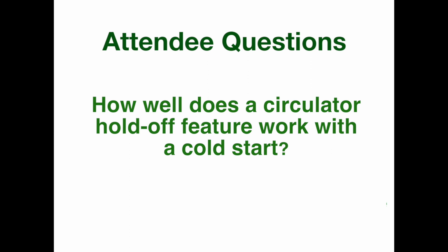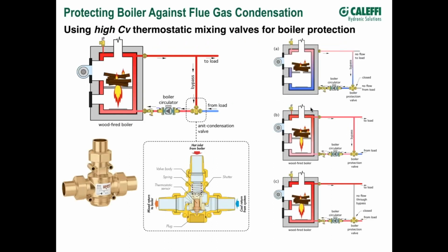Yeah, if you go back to that, there you go. I think the Caleffi one we offer comes with a 130, and I believe you can get two other temperatures. I think you can get down to 115 and maybe a higher temperature. And I've got this exact thing going on in my system. I put that valve in there with the 130, and what happens? It's got an 18 degree differential, I guess.